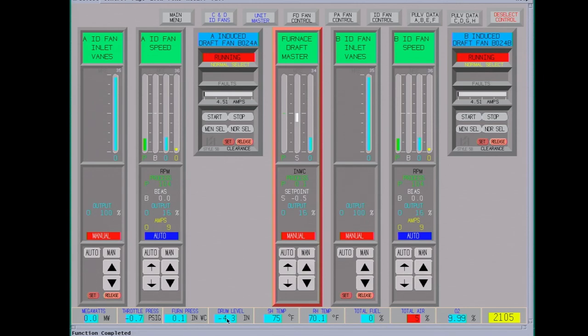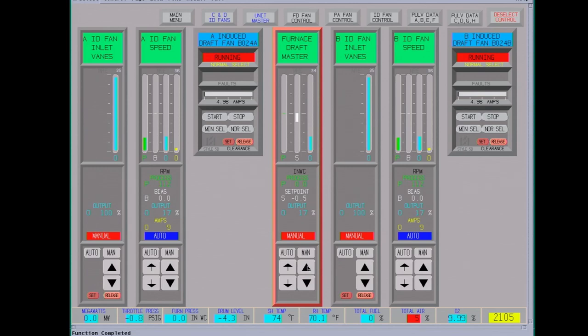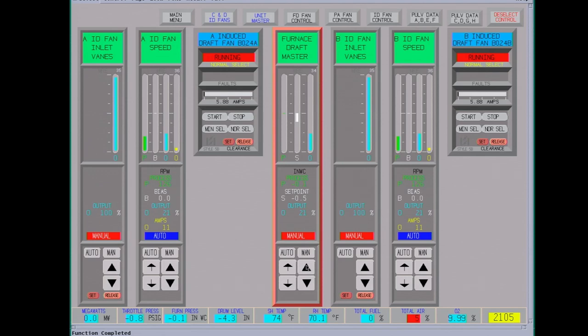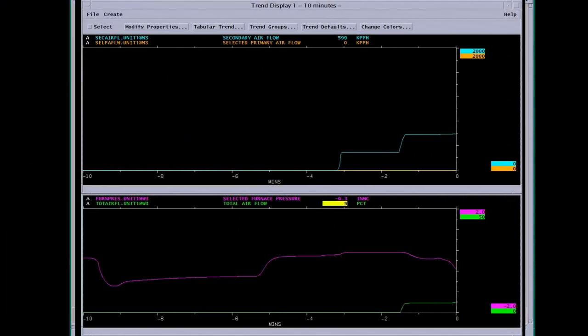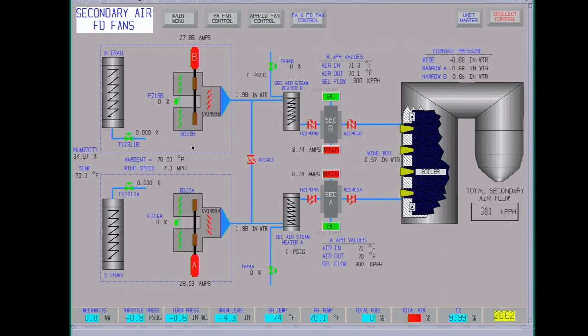Down here, drum level's at negative 4.3. There are limits. It has to be above negative 4.5 to get a permissive to start the igniter. Hopefully we get this thing to run in auto when we start putting the air to this. Sometimes just have to help it out a little bit. Put it back to auto, and that should control. Okay, back to the forced draft fan page.